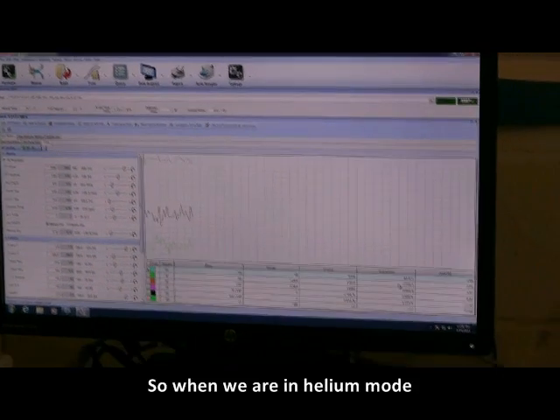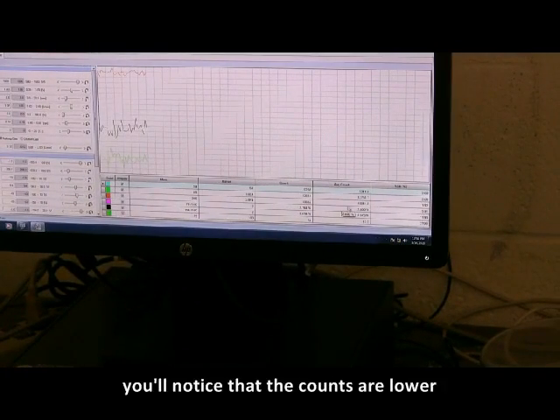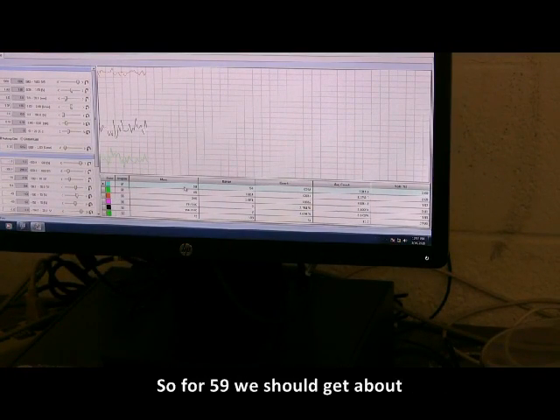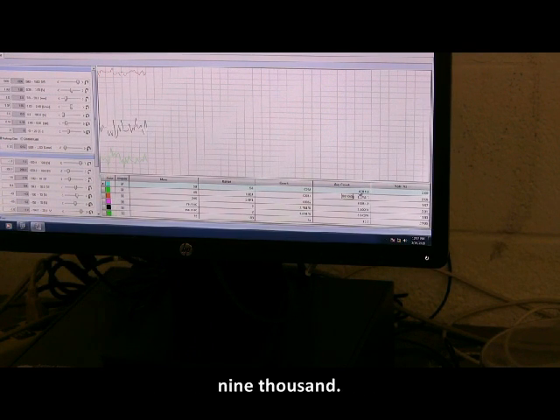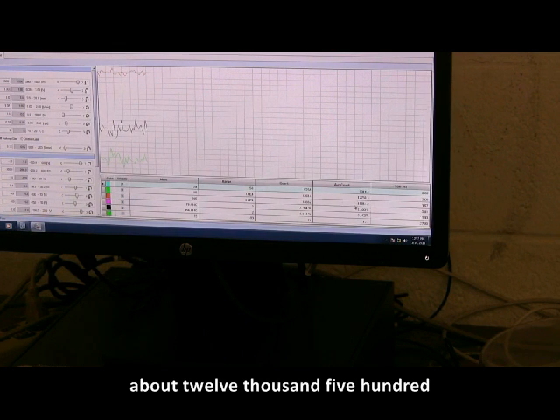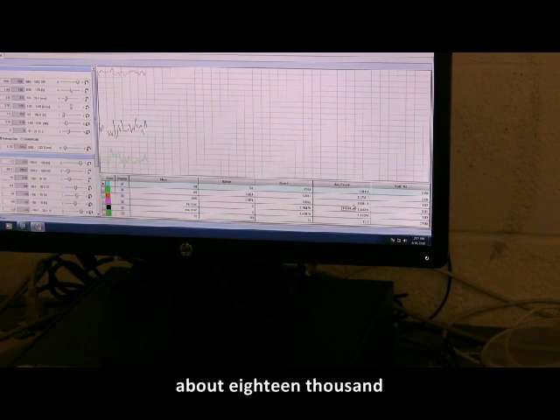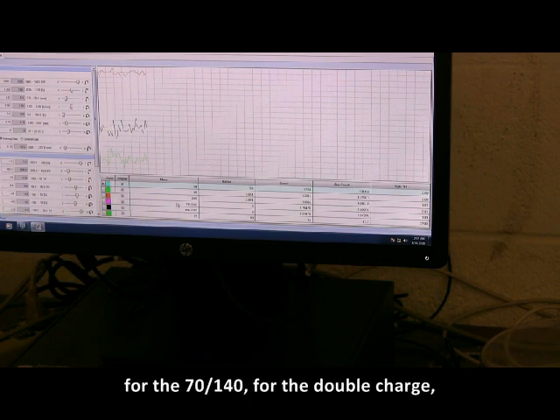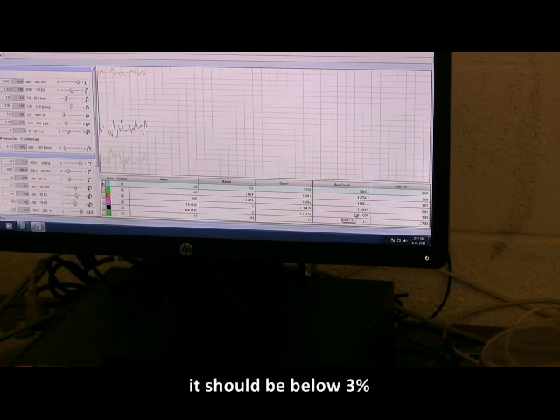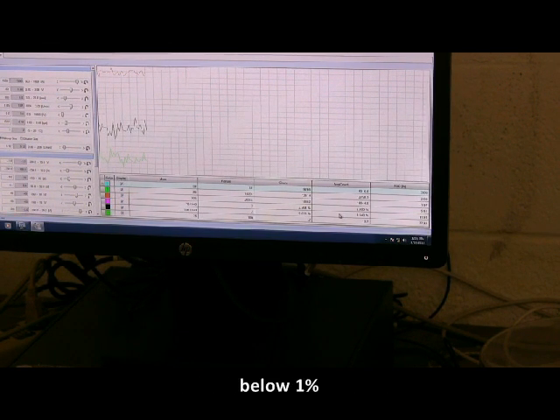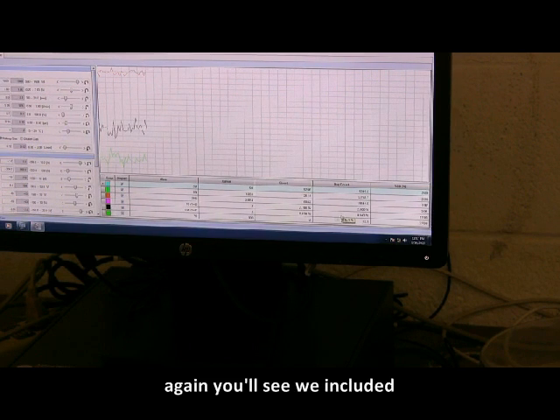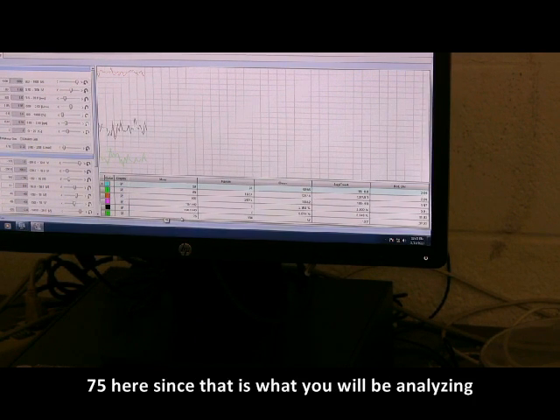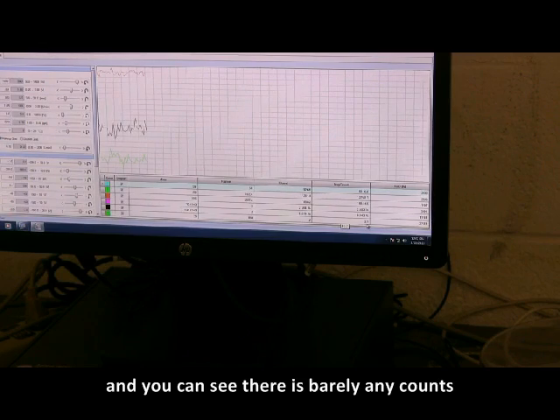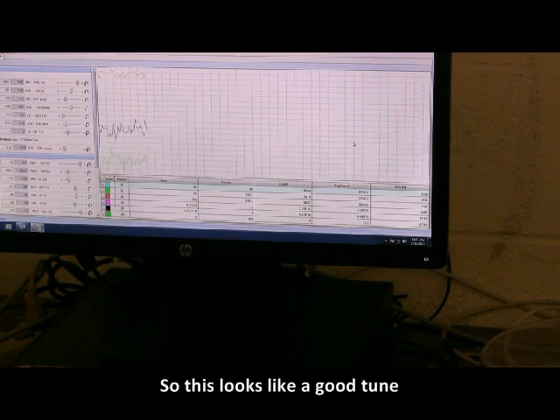So when we're in helium mode, you'll notice that the counts are lower. That's okay. So for 59, we should get about 9,000. 89 should be about 12,500. And for 205, we should get about 18,000. For the 70/140, for the double charged, it should be below 3%. And for 156/140, it should be below 1%. Again, you'll see we included 75 here since that's what you'll be analyzing. And you can see there's barely any counts. So this looks like a good tune.